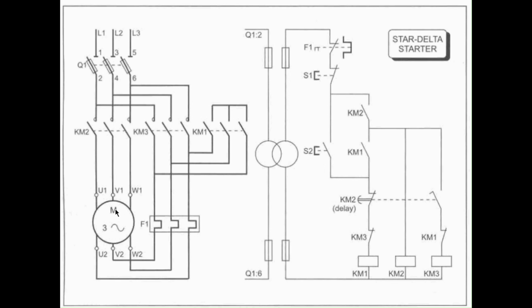Now, if this was to be run for an extended period of time with 1/3 of the torque, we would end up in an overload situation, as the motor will be matched to a given load, and effectively we are now 66% underloaded. So we must change over, and we do so as described in the control circuit. And then we've gone through that band of inrush current, the motor is up to speed, and then we have full torque available.